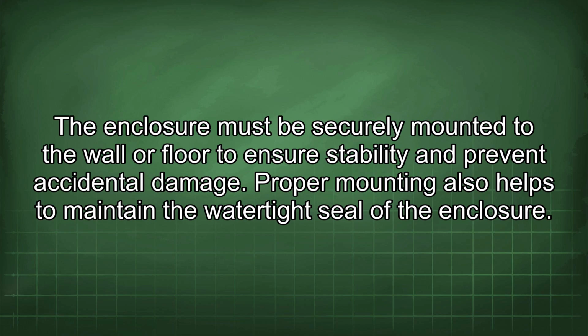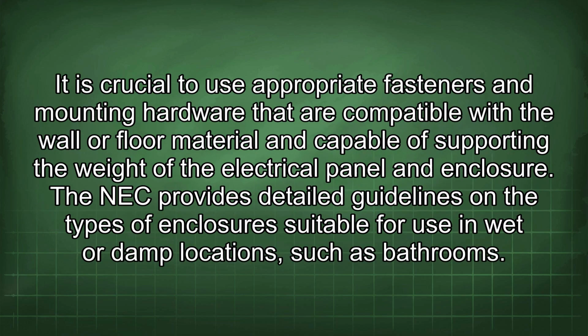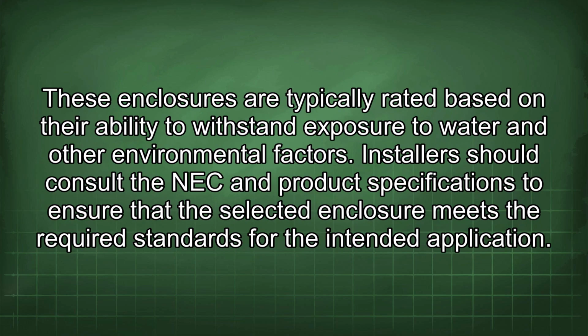The enclosure must be securely mounted to the wall or floor to ensure stability and prevent accidental damage. Proper mounting also helps to maintain the watertight seal of the enclosure. It is crucial to use appropriate fasteners and mounting hardware that are compatible with the wall or floor material and capable of supporting the weight of the electrical panel and enclosure. The NEC provides detailed guidelines on the types of enclosures suitable for use in wet or damp locations, such as bathrooms. These enclosures are typically rated based on their ability to withstand exposure to water and other environmental factors.